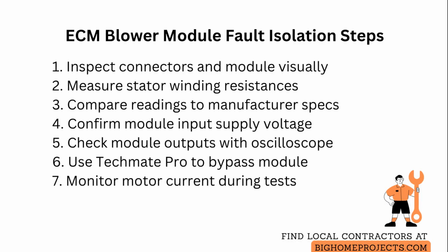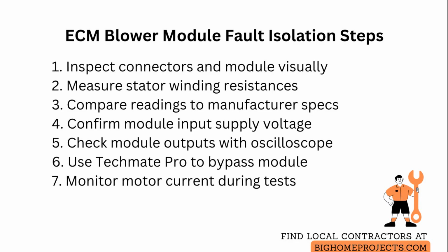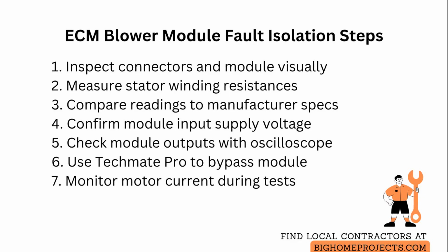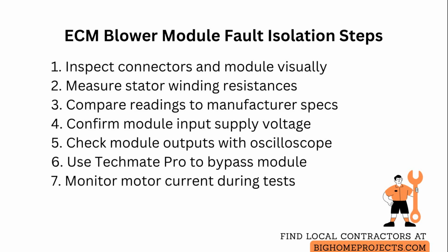Check the module outputs for pulse width modulated drive signals or three-phase outputs depending on the motor design using an oscilloscope or a quality meter capable of reading switching waveforms, so you can see whether the module is commanding the motor under different speed commands.